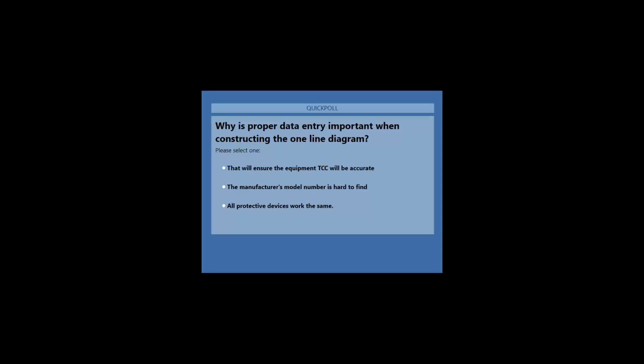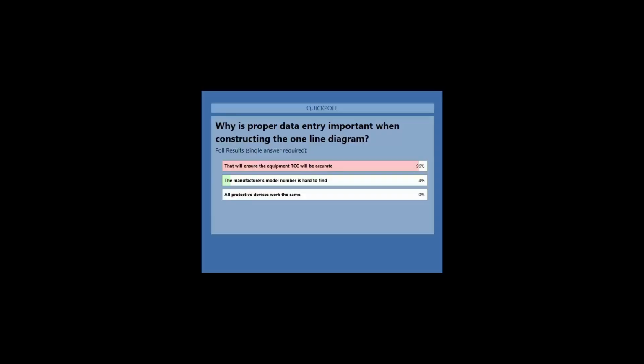we can collect. And frankly, when you're doing an arc flash study, the data collection portion can be 50% or more of the time involved in doing the study itself. And that's because on older systems that haven't received a study before, it's sometimes difficult to get all the data. So the more data that can be collected, the better job you can do both for coordination and for mitigation.